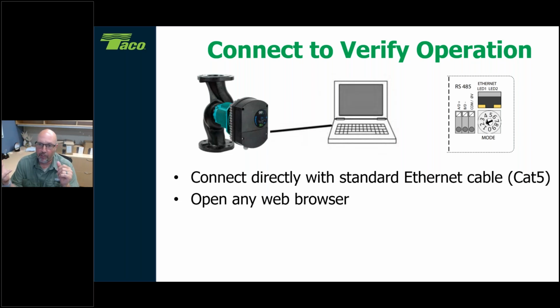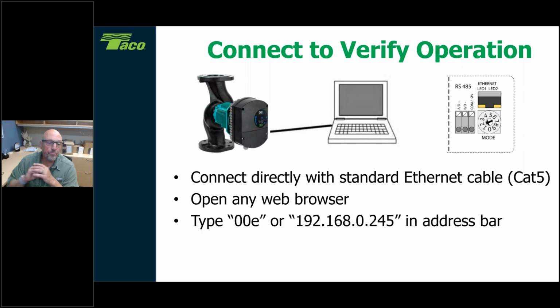whichever ones that are out there right now, Safari, you open up that web browser and you type in one of two things. So you type in the words OOE or the IP address of the circulator, and every circulator has this IP address of 192.168.0.245. They all come that way out of the box from the factory. You type in any one of those things. Now, you do not need to be online, all right, because yes, we're going to find these circulators installed in a mechanical room. There's not a lot of Wi-Fi down there.